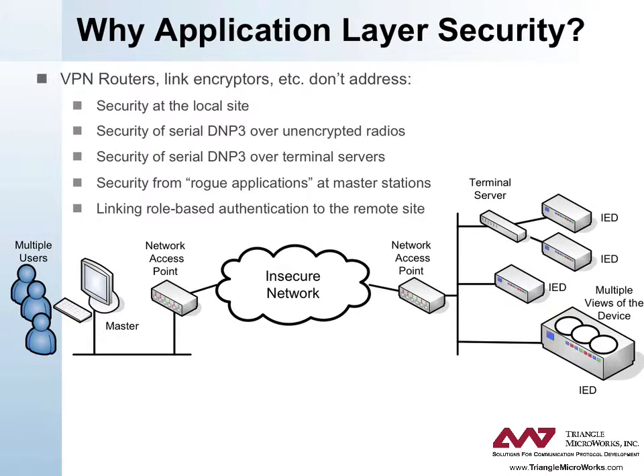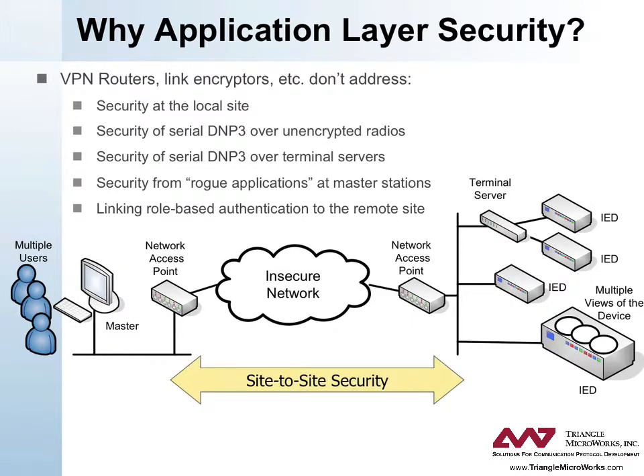There are three types of security that are commonly deployed in communication networks today. Site-to-site security includes the use of Virtual Private Network (VPN) routers and protocols such as IPsec to secure the link between two locations — for example, a corporate office and a home office, or a master station and a substation. It does not secure the networks at those two locations, and physical security measures like locks and guards are necessary to protect them.